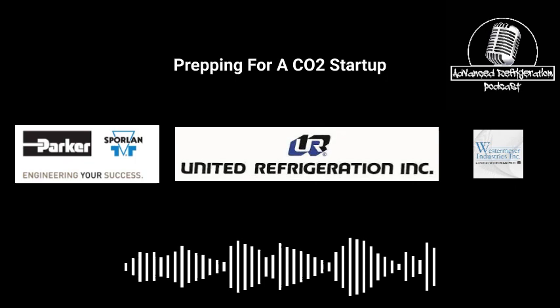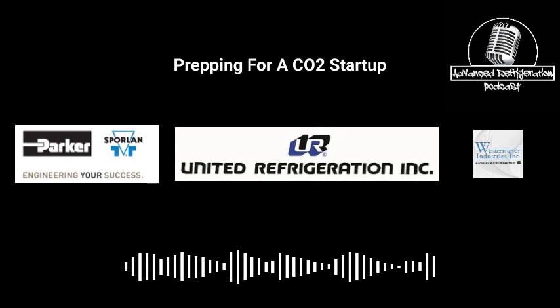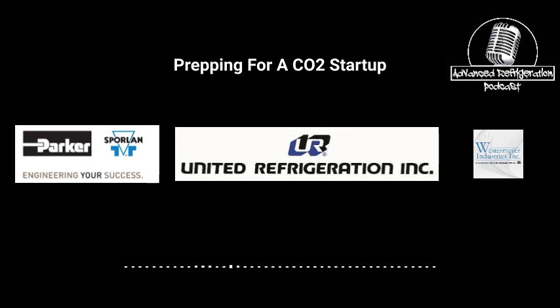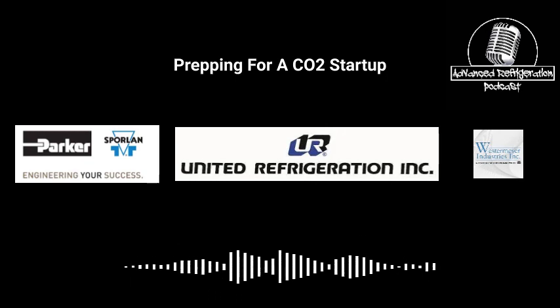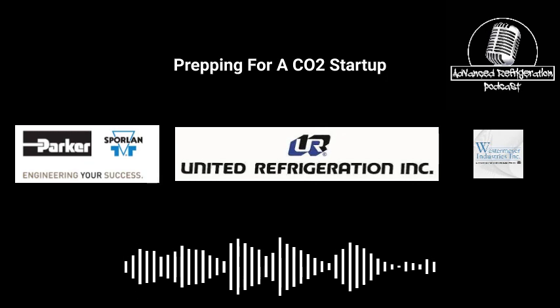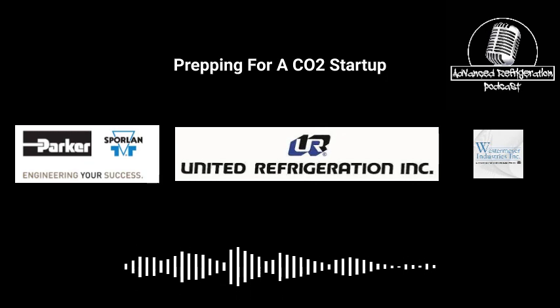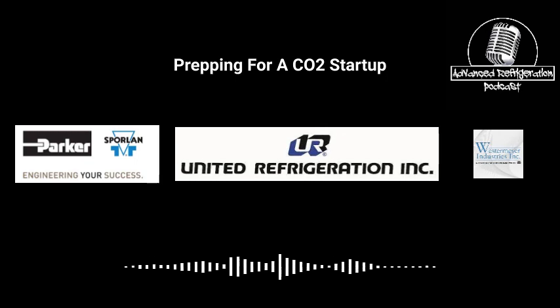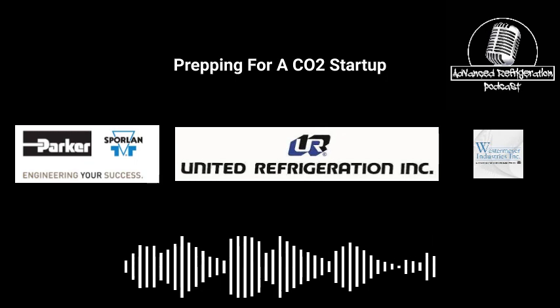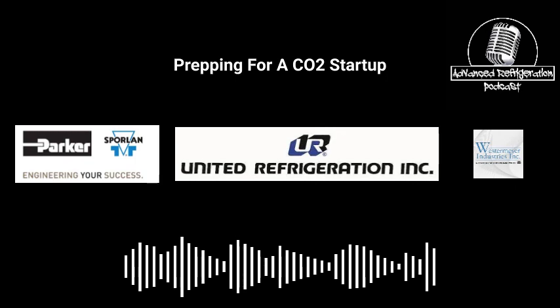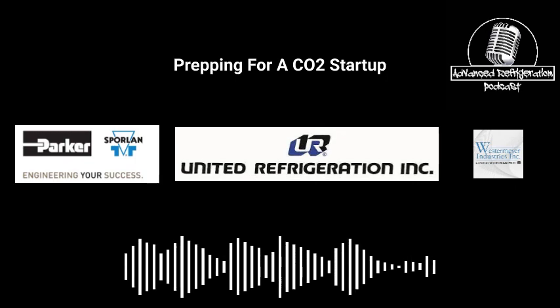I mean, just going through and checking all that stuff, and then slowly starting this thing up and watching it. Make sure your gas cooler, I forgot that part, make sure the gas cooler's programmed. If it's a Güntner, call them and get them to send you the program. And if it's anybody else, the BACs are super simple. You just tell it you're giving it a 0 to 10 inverted if it's got to be that way. Make sure the fans ramp up and down before you start it. Make sure you have complete control over the fans. You do want to make sure the dump valve for the water is working properly. You want to make sure the pressure regulator for the flow is set properly. So there's some other things that you need to do.